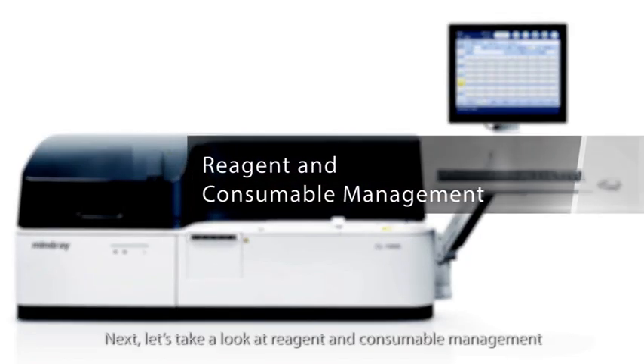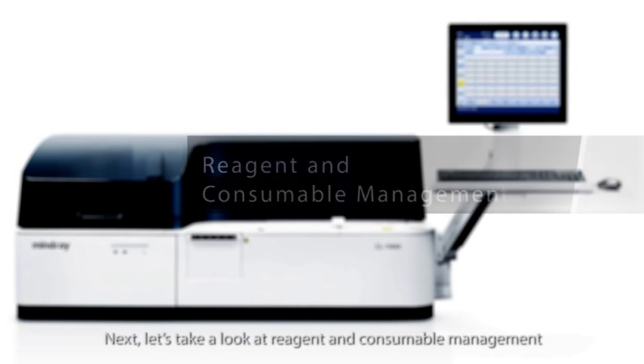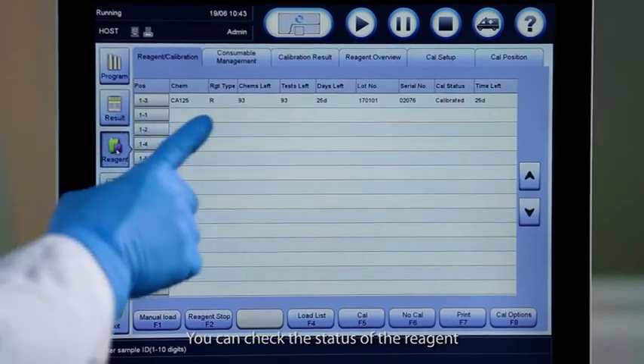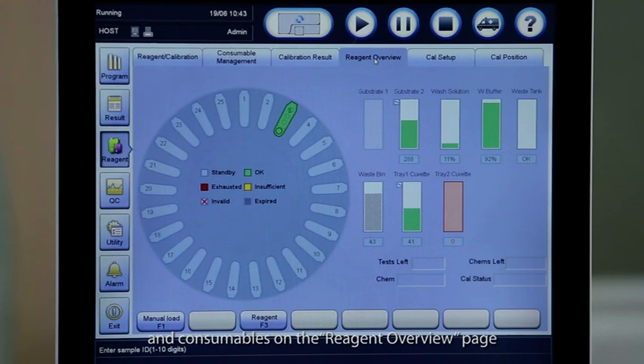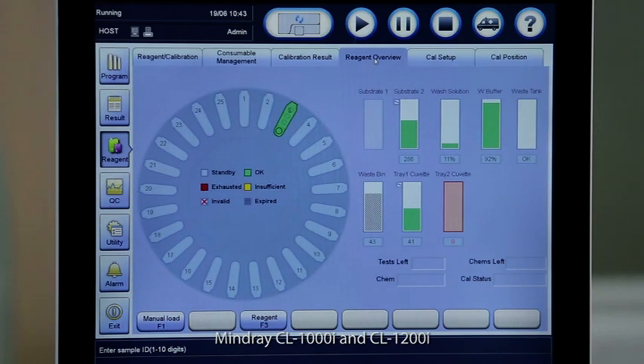Next, let's take a look at reagent and consumable management. You can check the status of the reagent and consumables on the reagent overview page. Mindray CL1000i and CL1200i use five kinds of consumables.